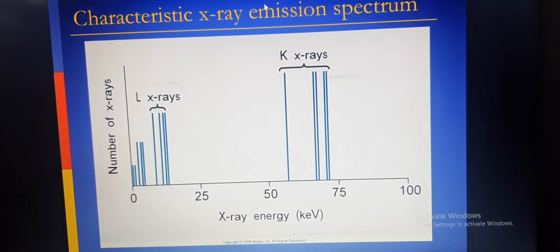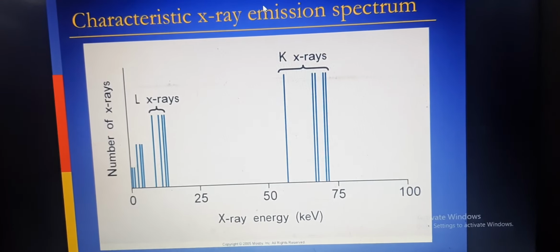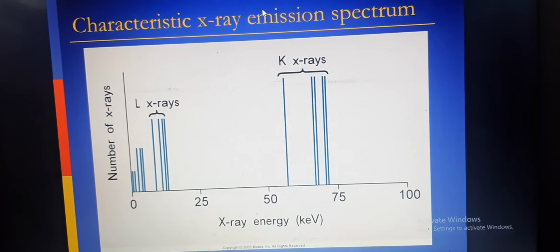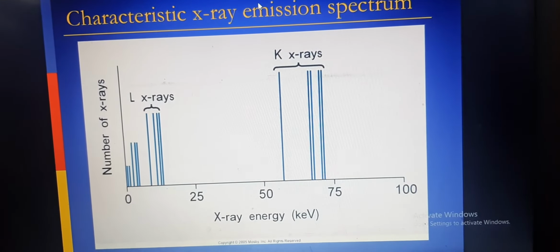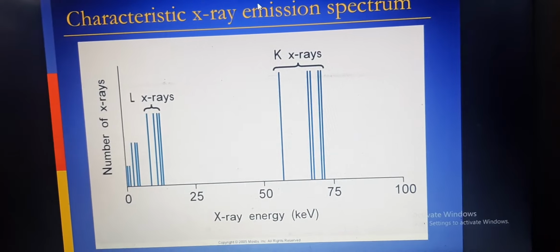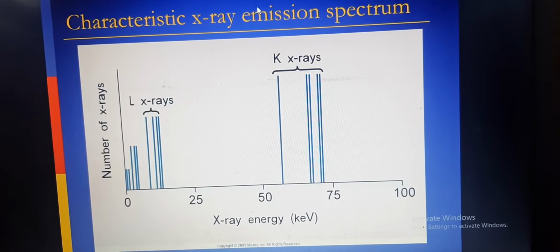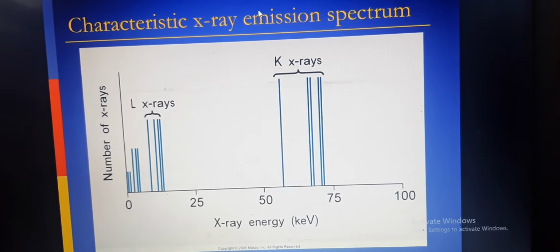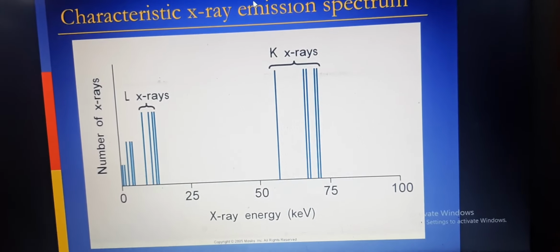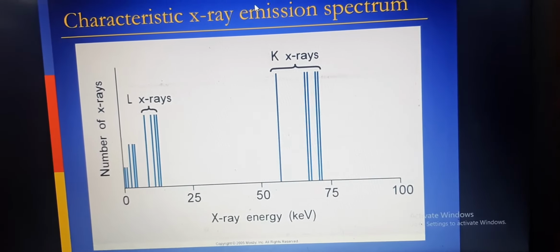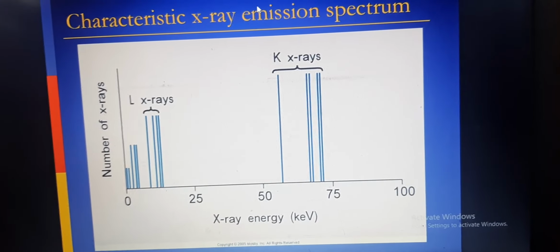representing the L X-rays. The other lower energy lines represent the characteristic emission from the outer shell electrons, which is very low energy. The relative intensity of K X-rays is greater than the lower characteristic X-rays because of the nature of the interaction process. K X-rays are the only characteristic rays of tungsten with sufficient energy to be of value in diagnostic radiology.